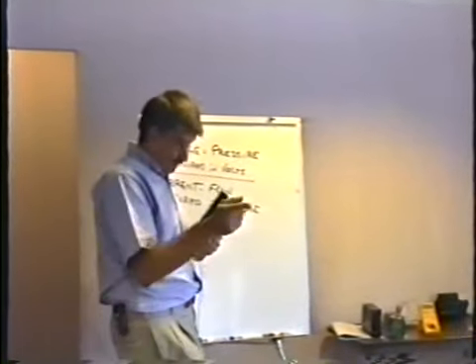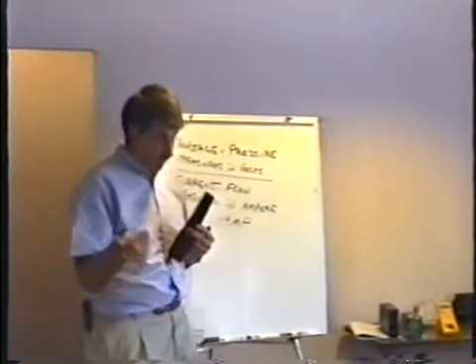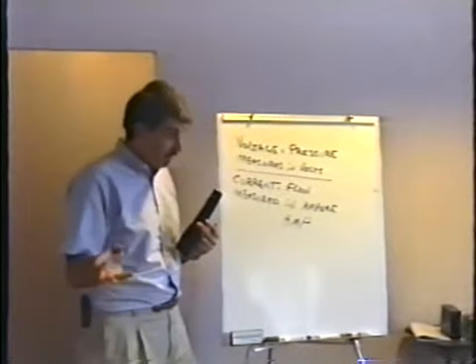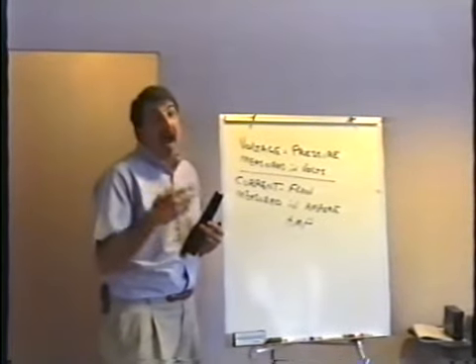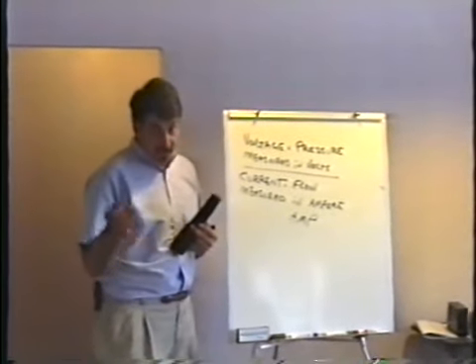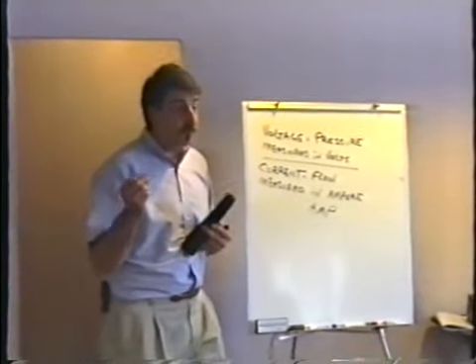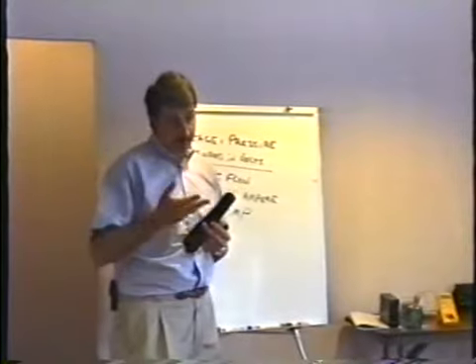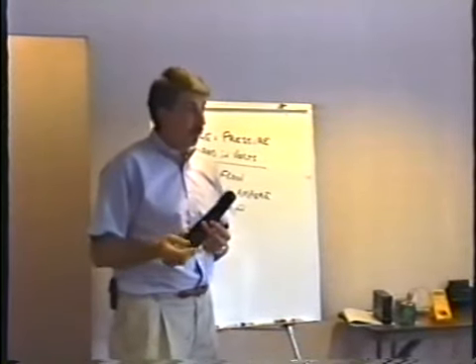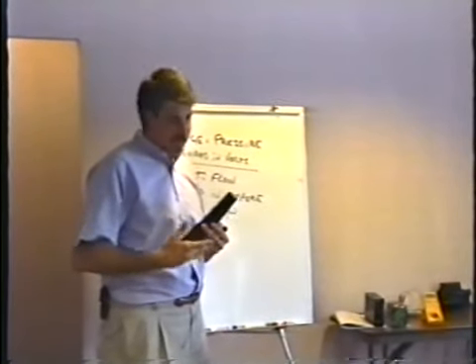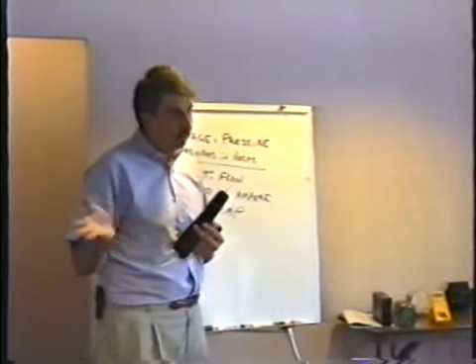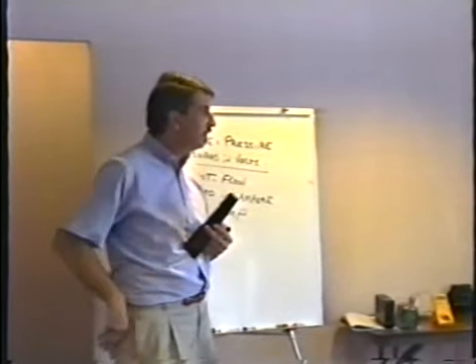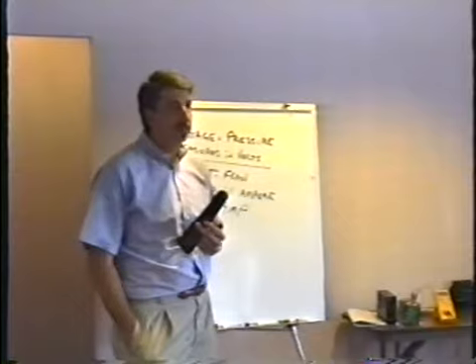This is especially important for those of you working in arcades or setting up arcades. How many games can you put on one circuit breaker? If you have a 20-amp breaker, if you put 10 games on there, you'll be fine — 10 or less.